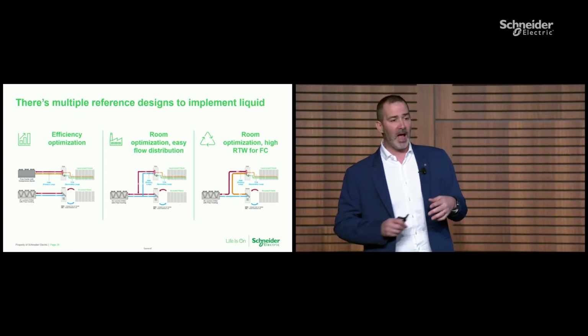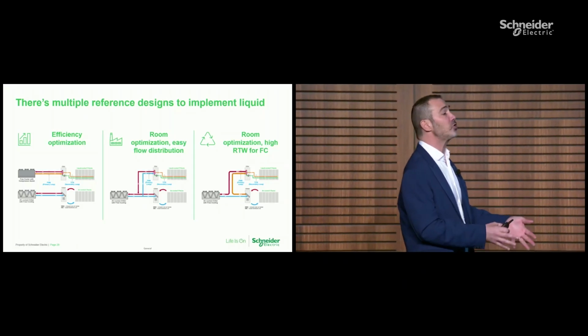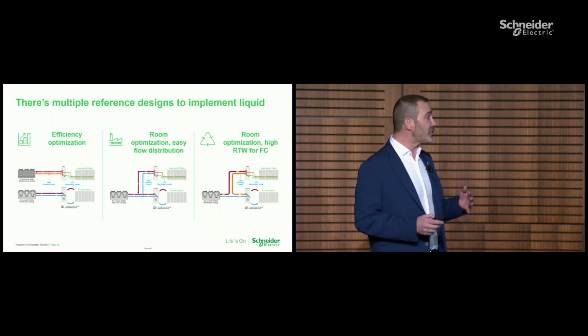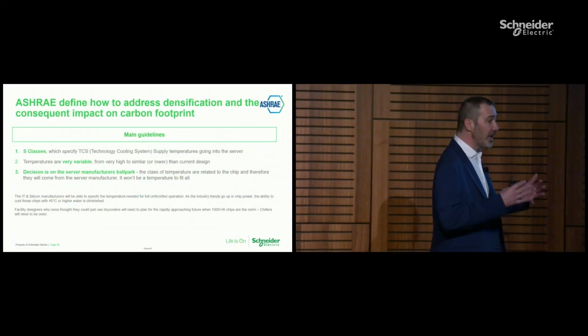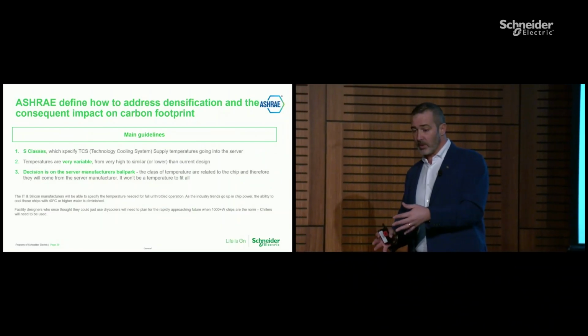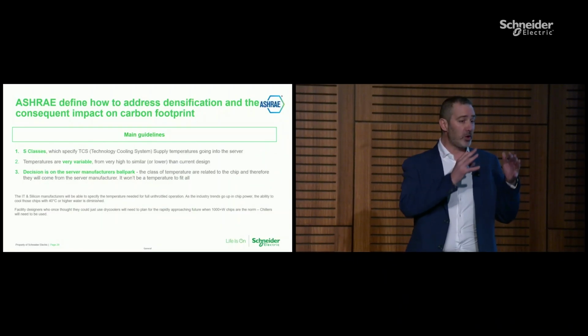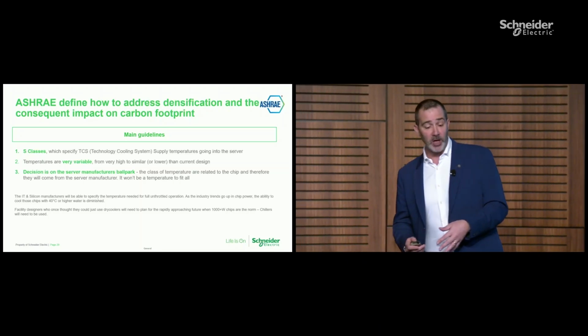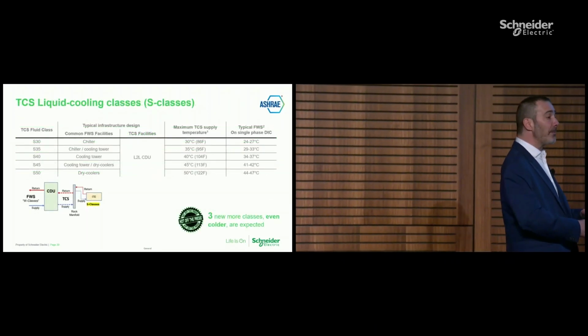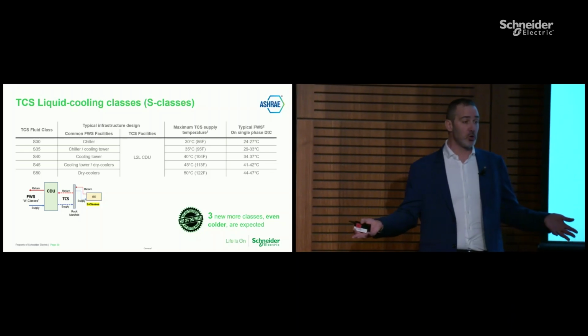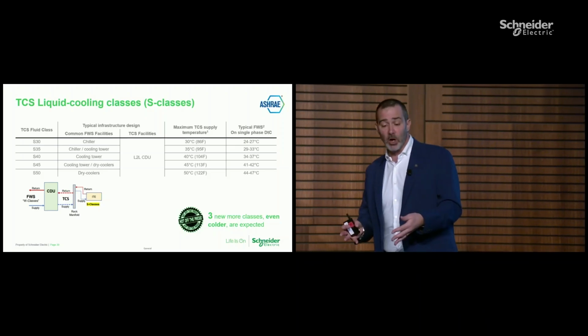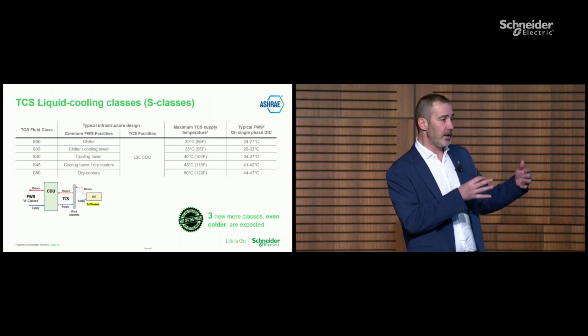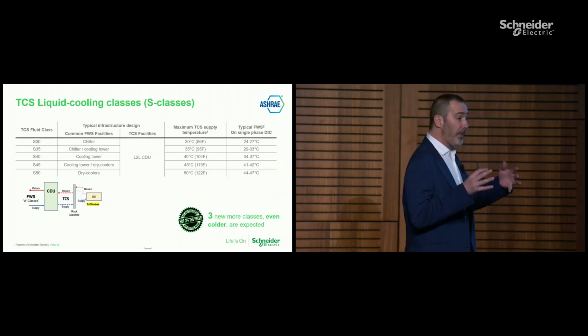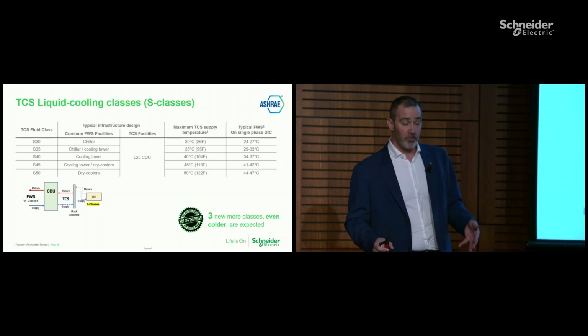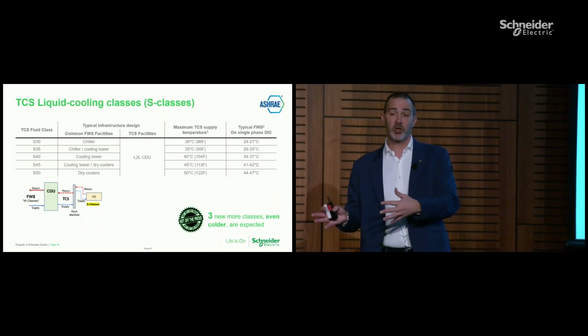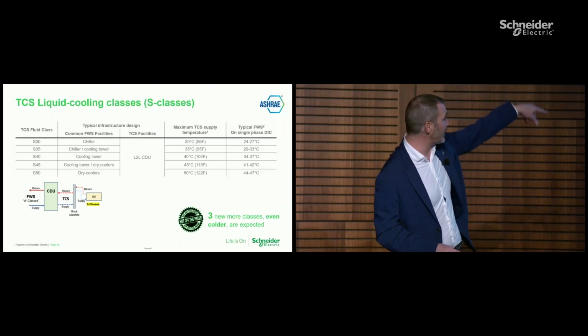And that's question number one everybody in the ecosystem has. And unfortunately, there is not a clear answer on that. ASHRAE tried to answer, but they did not answer. ASHRAE said it is up to the server manufacturer to determine the temperature. So they classify the servers according to some classes, which are called S, like silicon. And these classes define when and how to design the chiller and the heat rejection unit. The problem is that in many cases, when you design a data center, you don't know which server will be installed. So you don't know which class you need to consider.